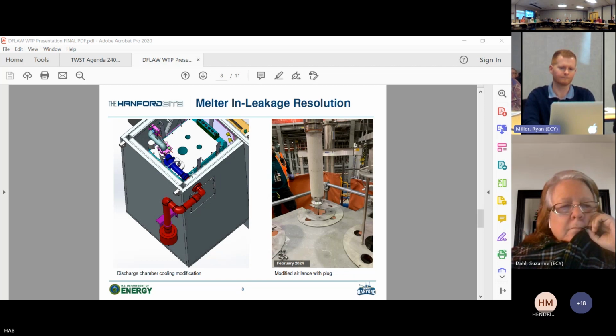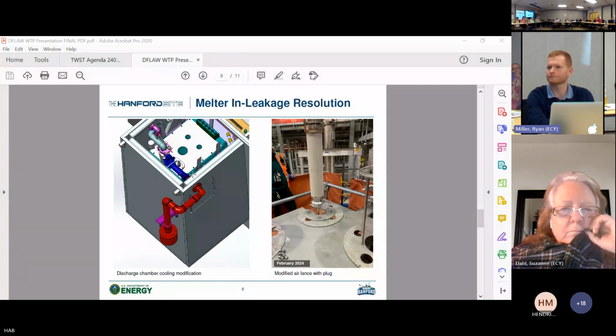They are also creating a mitigation. There's another way this kind of system could be sealed, using epoxy on the outside of the pipe. That would require drilling a hole, not cutting out the whole panel, then applying the epoxy using a borescope and some tool to apply it. So we'd have a second layer of defense if we have to go down that path. But we didn't exercise that, I'd rather not cut into the structural part of the discharge chamber if we can avoid it. So I know that's not a perfect answer.